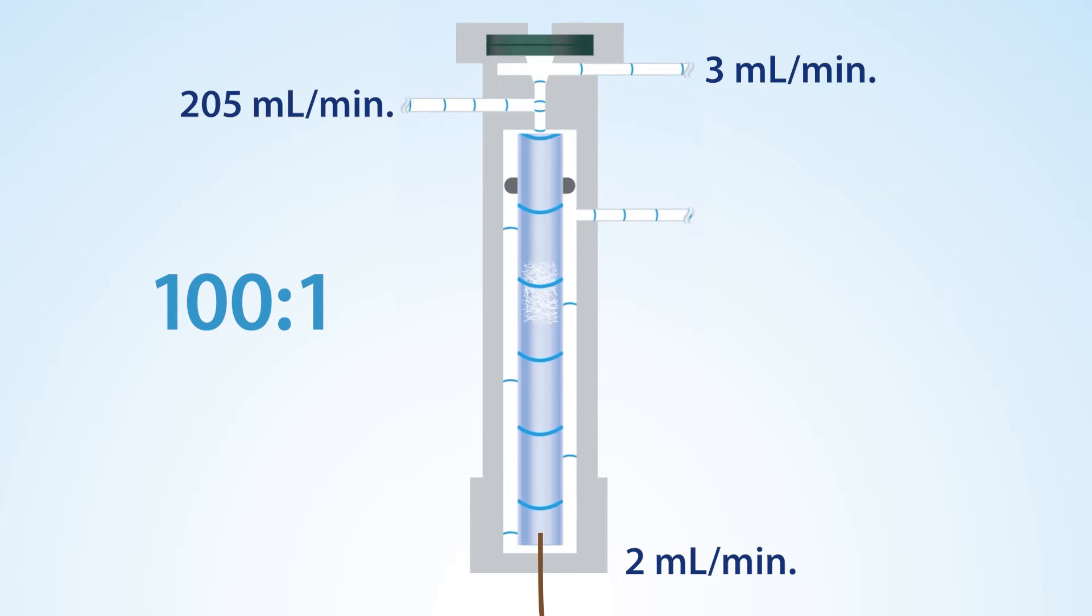Let's look at an example. Here, we're running an analysis with a 2 milliliter per minute column flow and a 3 milliliter per minute septum purge. We have a 100 to 1 split ratio and a total helium flow of 205 milliliters per minute.